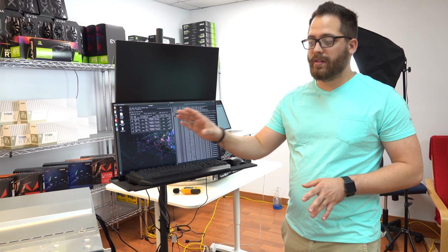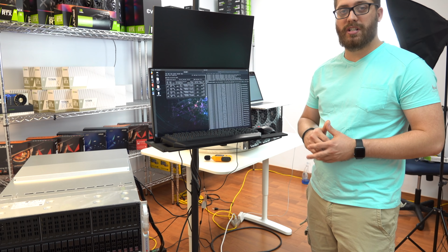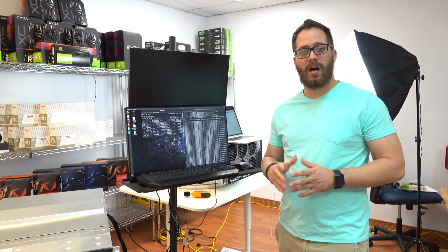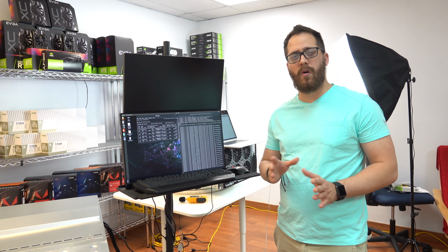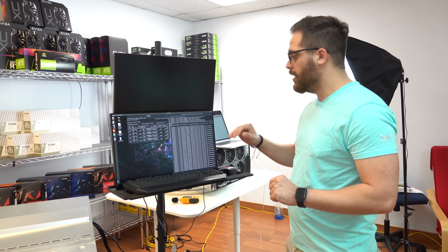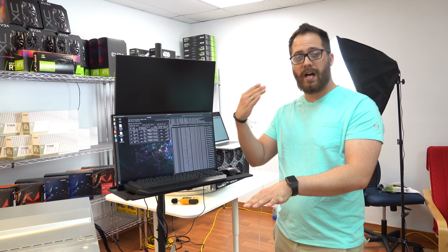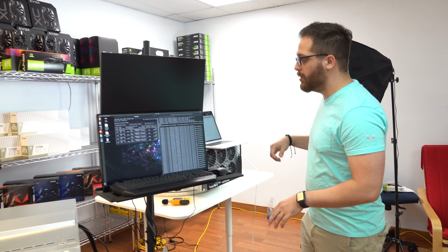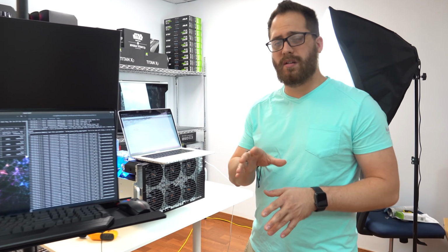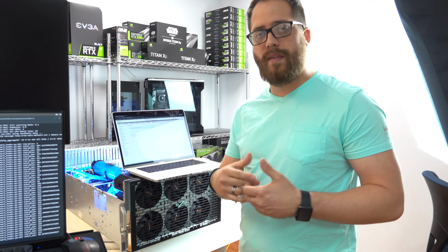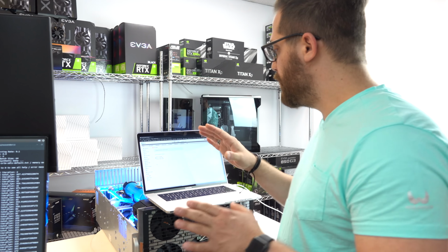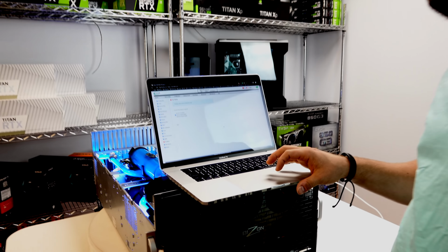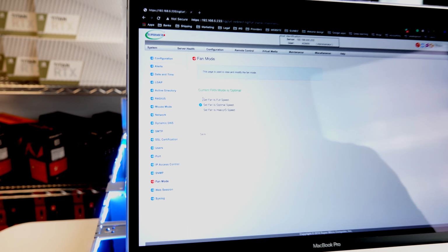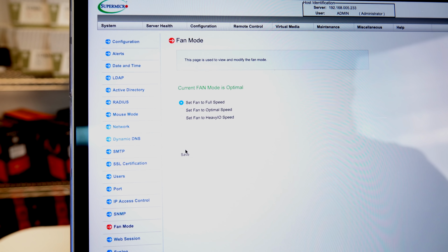So people say that with this server, for the Titan RTX, if you speed up the fans of the server to the maximum, you get better performance. Now we're going to try that. What we're going to do is, in default mode, go to the computer with the IPMI, a built-in software that Supermicro has on the server. We're going to put the fans to the maximum, full speed, and check if the performance changed or not.